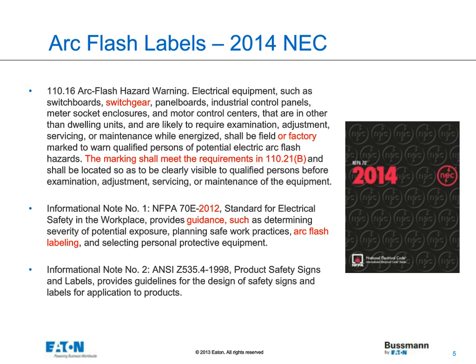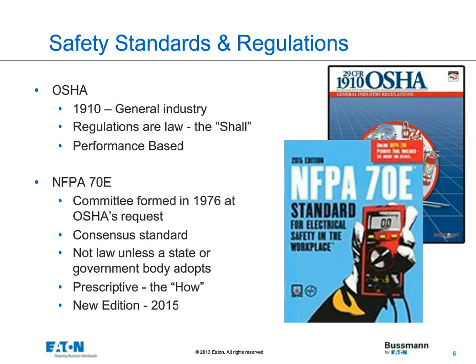Moving on to the next slide, we have to deal with the safety standards and regulations. That's really what's going to drive this presentation this morning. What are the OSHA requirements and what are the NFPA 70E requirements? As you can see here, OSHA is the regulation. This is the law, if you will, and as such, this is often termed a shall. One issue with the OSHA requirements is that they are performance-based. They tell you what you have to do, but they don't tell you how to comply. That's where 70E comes in. 70E is often referred to as the how. It's not required to be adopted as far as the law is concerned, but it's typically the most logical choice to use when it comes to complying with the OSHA requirements. So it shows you how to comply. And of course, as mentioned earlier, the new edition is the 2015 edition.